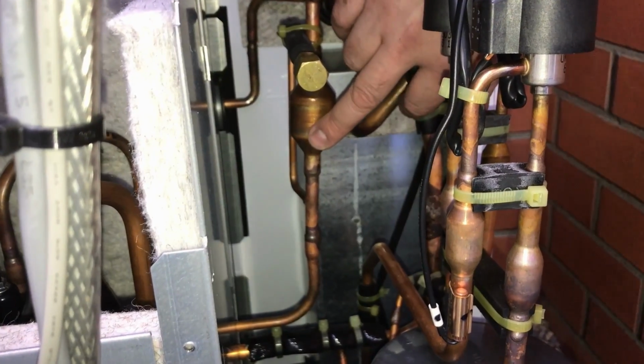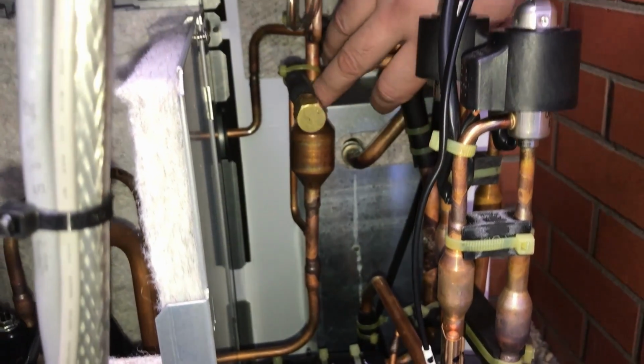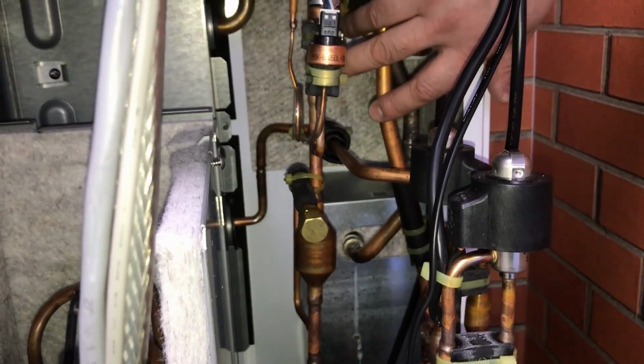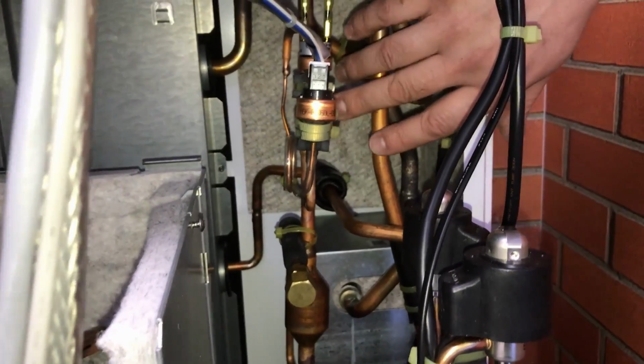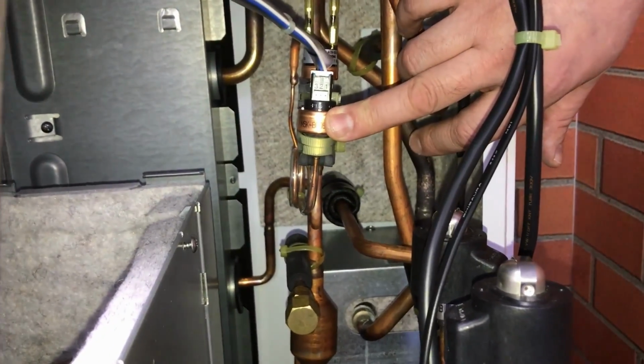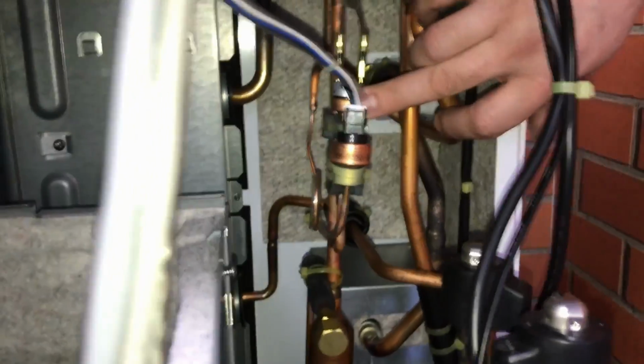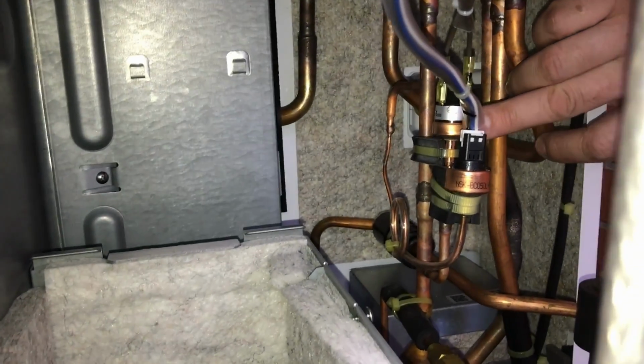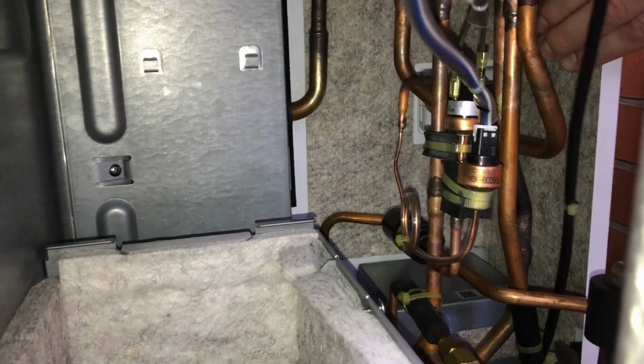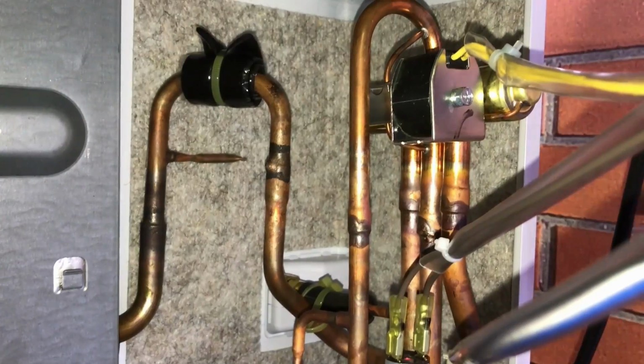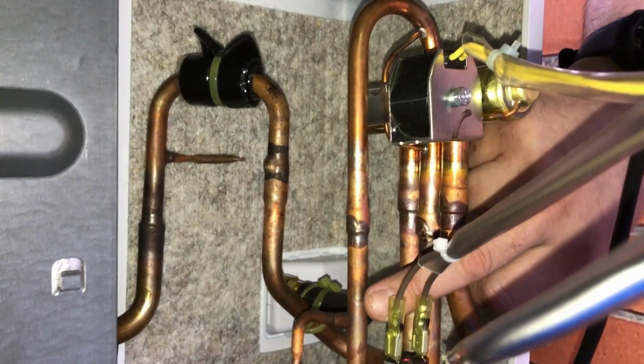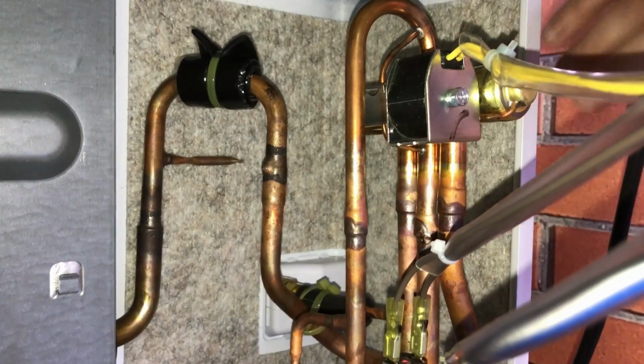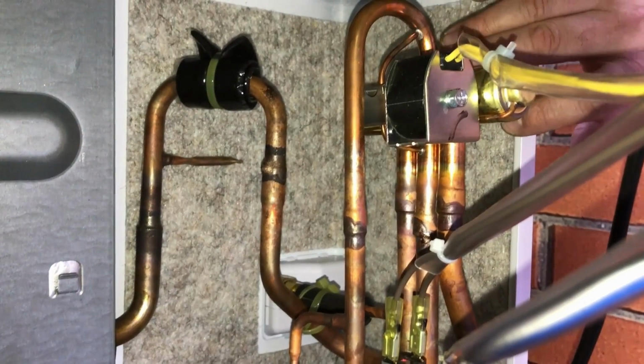First thing it comes up to there is a muffler, and there's still nice hot vapour. It's going to pass my high pressure sensor, so that's a pressure transducer, and it's going to pass my high pressure switch, so that's going to be my safety, so it's measuring what's going on with that refrigerant. There's my discharge pipework. It's going to go from there up to my reversing valve. It heads in through the top of there.